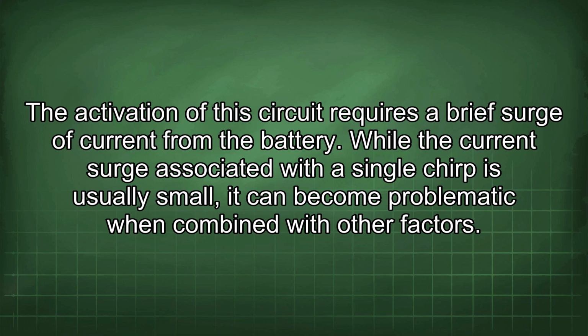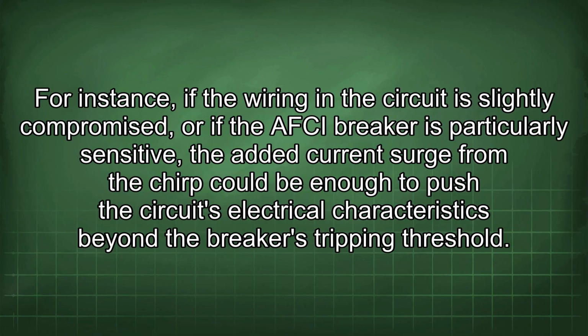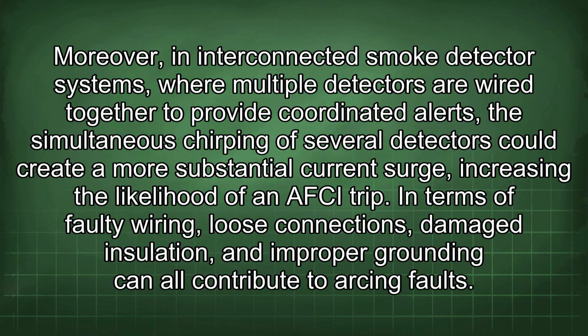While the current surge associated with a single chirp is usually small, it can become problematic when combined with other factors. For instance, if the wiring in the circuit is slightly compromised, or if the AFCI breaker is particularly sensitive, the added current surge from the chirp could be enough to push the circuit's electrical characteristics beyond the breaker's tripping threshold. Moreover, in interconnected smoke detector systems, where multiple detectors are wired together to provide coordinated alerts, the simultaneous chirping of several detectors could create a more substantial current surge, increasing the likelihood of an AFCI trip.